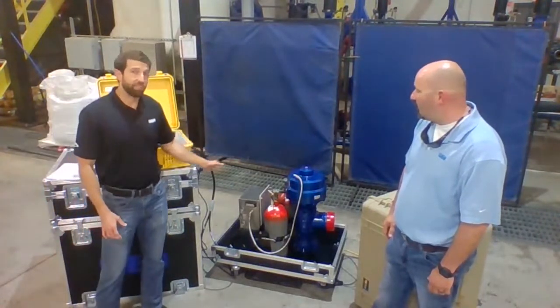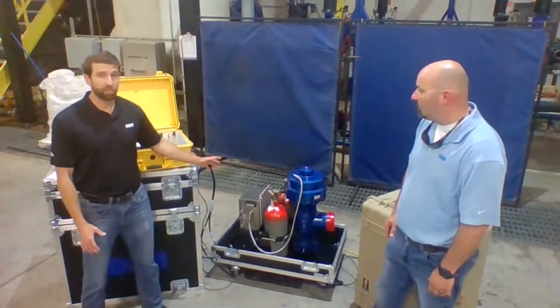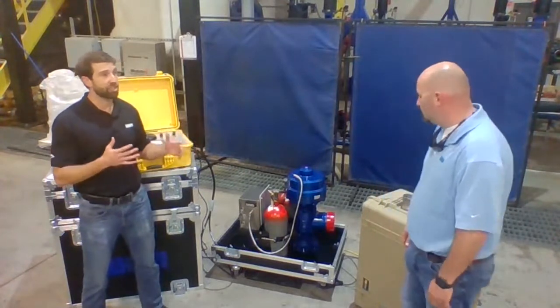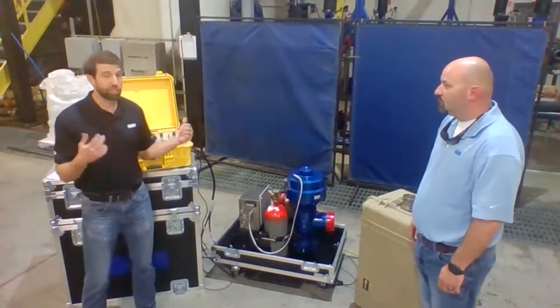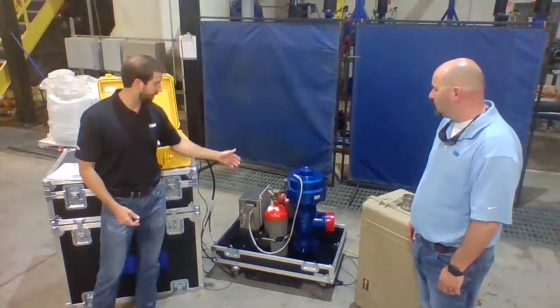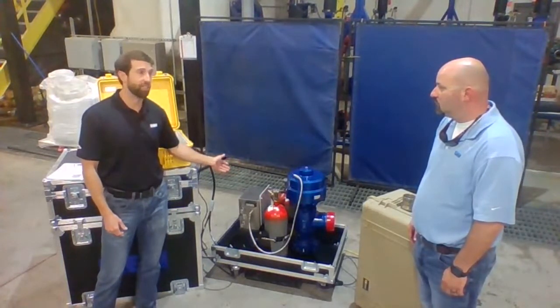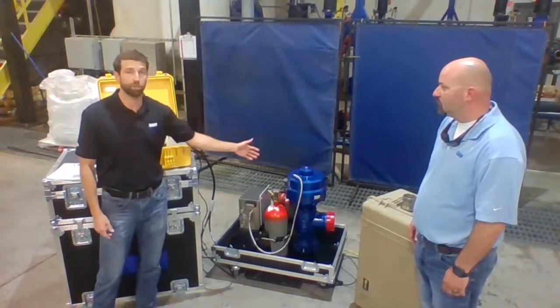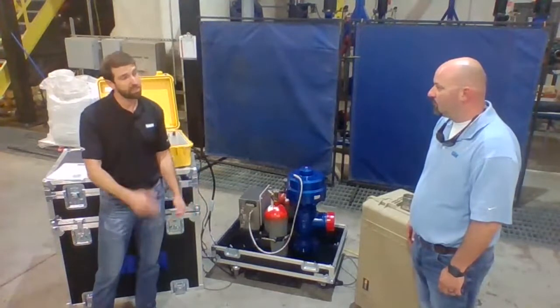Once you have the valve box and control box hooked together, the next thing you need is to get your nitrogen set up. It's just 2 hoses: one runs from a nitrogen bottle into your valve box, and the other runs from the valve box into your relief valve.